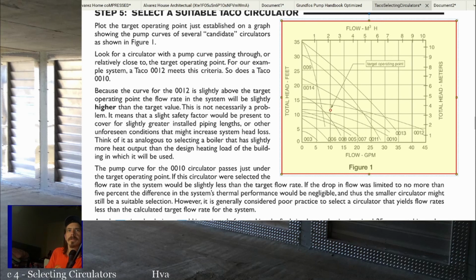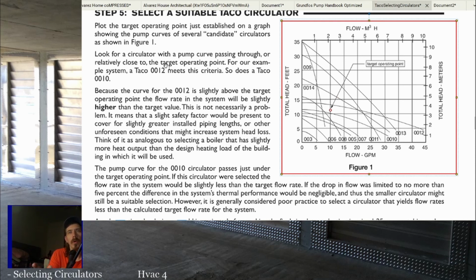Oh, no, that's not what I wanted. All right. So anyway, this operating point right here. So you plot your operating point on the graph with your pump curves, and then you look for a circulator with the pump curve passing through or close to the target operating point.